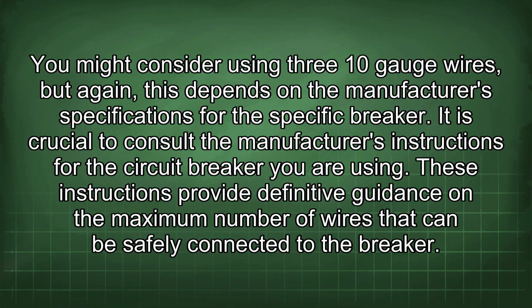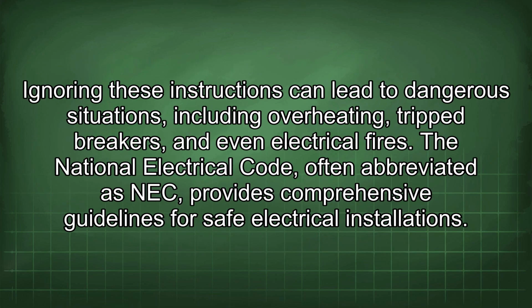It is crucial to consult the manufacturer's instructions for the circuit breaker you are using. These instructions provide definitive guidance on the maximum number of wires that can be safely connected to the breaker. Ignoring these instructions can lead to dangerous situations, including overheating, tripped breakers, and even electrical fires.